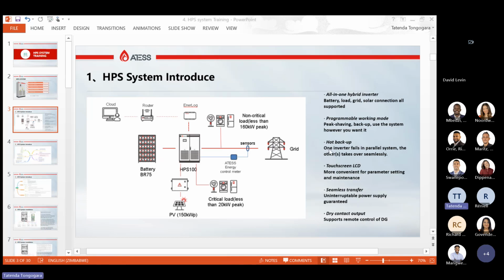So the HPS has a programmable working mode that is peak shaving, backup. You can use it load first. I will show you the working modes that we have on the next slides. And then we also have the touch screen where you change your parameters. It allows a seamless transfer, 20 milliseconds. But I'll explain what you need to do on your design when you're designing your system to get those 20 milliseconds seamless transfer. And then it also has the dry contact output, which supports remote control of your generator.